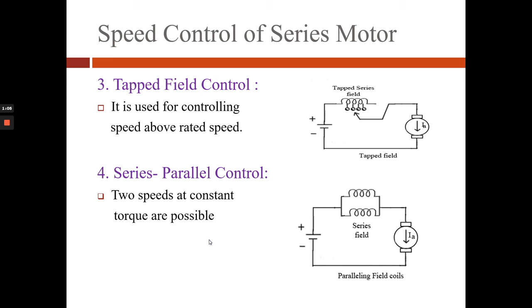Now we will see tap field control. As we move the selector switch from position 1 to 3 and so on, the number of turns of the field winding reduces, which reduces the MMF. Since phi is proportional to MMF, the flux decreases. As flux decreases, speed increases, so the motor speed increases as we move from position 1 to 5. In series-parallel control, two speeds at constant torque are possible.